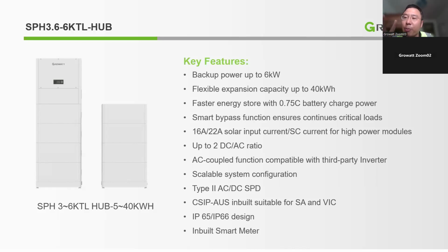Secondly, we provide manual Schneider, Australia-approved manual Schneider DC isolators at the main switch. If the end users realize the inverter is under maintenance or down, they can just use the manual switch at the main switch to switch the EPS port and EPS load back to being powered by the AC grid.